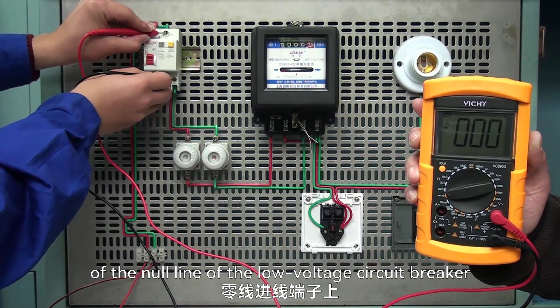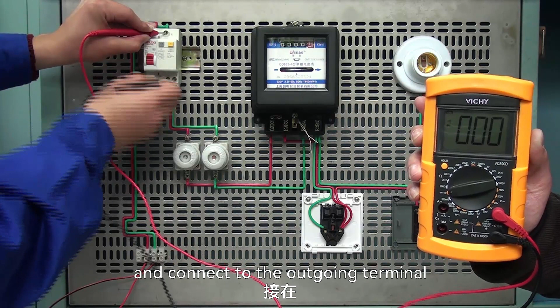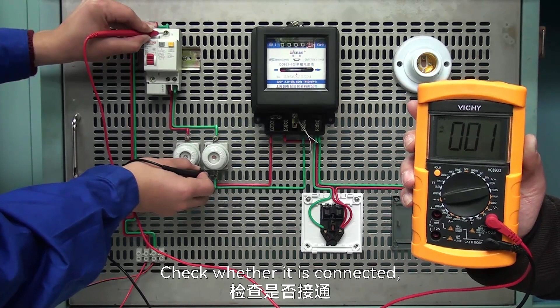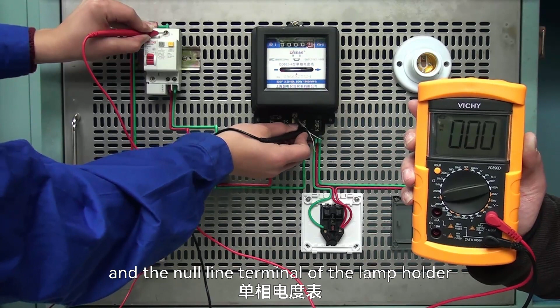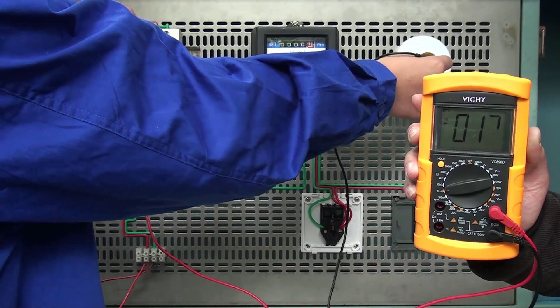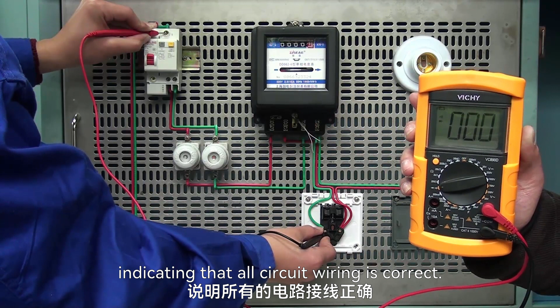According to the circuit diagram, and then connect to the incoming terminal of the null line of the low voltage circuit breaker with the red probe of the multimeter, and connect to the outgoing terminal with the black probe. Check whether it is connected, and check the low voltage fuse, single-phase electric meter, and the null line terminal of the lamp holder, one by one, according to the circuit diagram. In the end, check the wiring from the electric meter to the socket, and strictly follow the requirements of null at left and alive at right, indicating that all circuit wiring is correct.